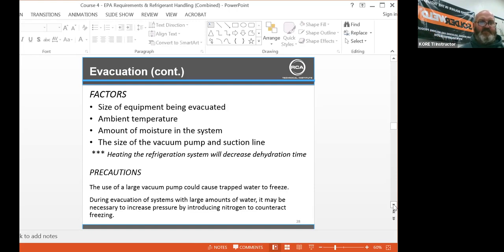Precautions: the use of a large vacuum pump could cause trapped water to freeze. During the evacuation of the system with large amounts of water, it may be necessary to increase pressure by introducing nitrogen to counteract the freezing. That's where we get into double and triple evacuations.